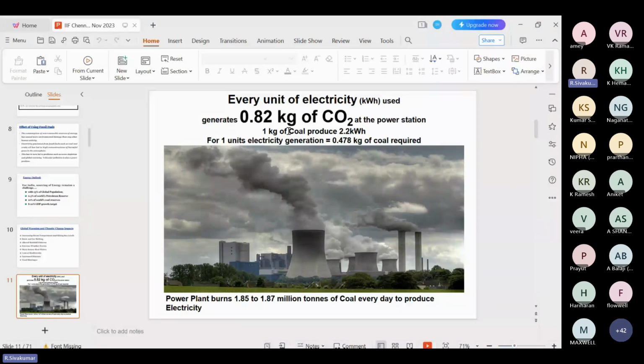In a power station boiler plant, every kg of coal should generate around 4.5 to 5 units of electricity. But practically they produce only 2.2 because of various losses associated with the power generation itself. Again, this generated power is transmitted from one point to another, at the state grid and national grid level, via high and extra high voltages, EHT. Even for transmission in the HT line, there are transmission and distribution losses. So there is a mantra: as a consumer, if we save 1 unit of electricity, we are avoiding 2 units of generation in the power plant. So even if we save 10 units per day in a plant, we are avoiding 20 units of generation in the power plant.